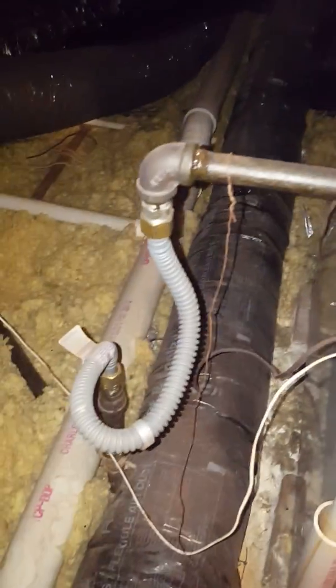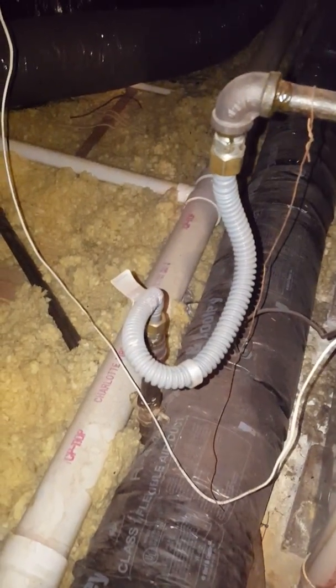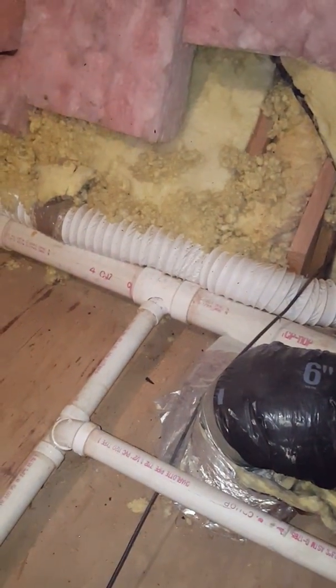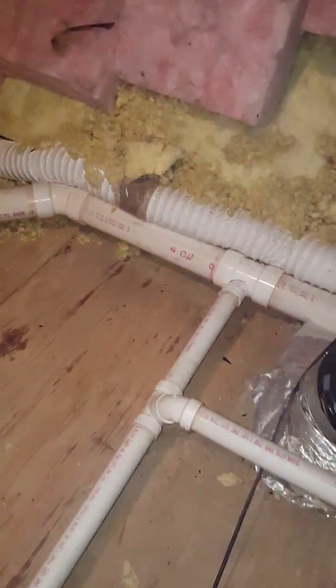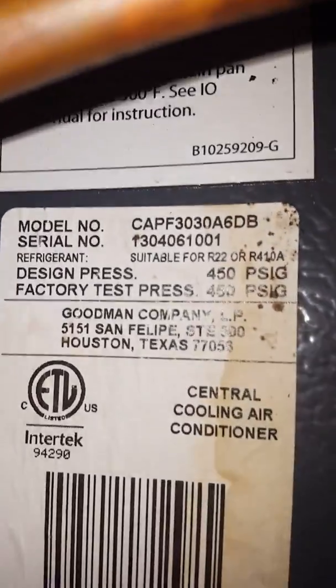There's a quarter-inch hard pipe, a half-inch hard pipe, and your electric attic pan. Condensate line running in. Don't know what that emergency drain is — other than maybe there's a second-floor hot water heater running into that chase over there. This looks like it drains down into the bathroom, but there is in the basement a label that says emergency drain line.